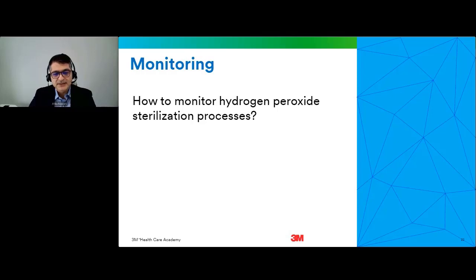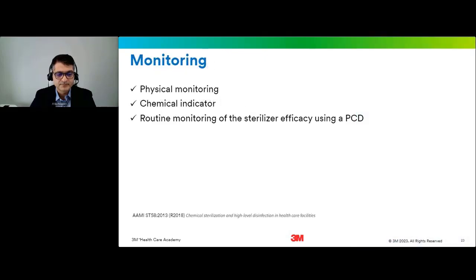So going to the last section of our presentation today, which is the monitoring piece. For monitoring, I will refer to the ANSI/AAMI ST58 document. ST58 mentions physical monitors include time, temperature, and pressure records, displays, digital printouts, and gauges. The rationale statement for this section is that physical monitoring provides real-time assessment of the sterilization cycle conditions and provides permanent records by means of chart recordings or digital printouts. Physical monitors are needed to detect malfunction as soon as possible so that appropriate corrective actions can be taken in the event of failures.